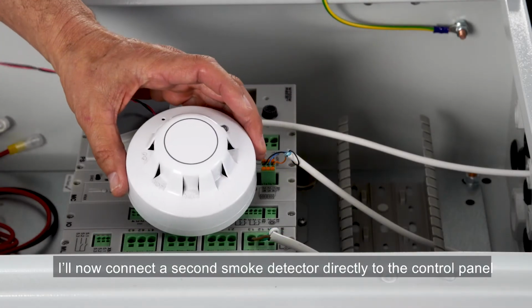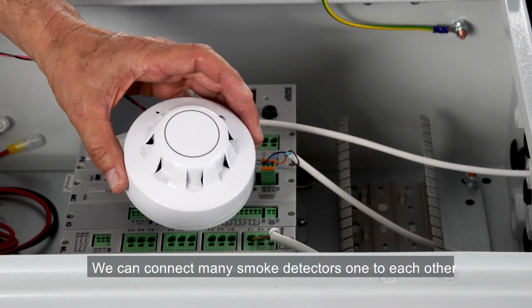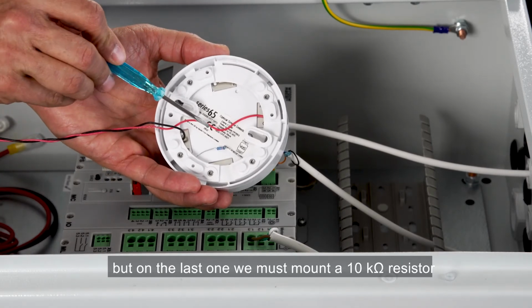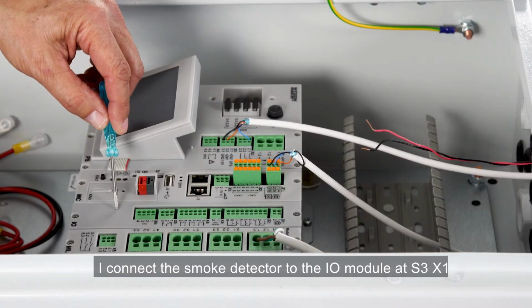I'll now connect a second smoke detector directly to the control panel. We can connect many smoke detectors, one to each other, but on the last one we must mount a 10 kilo ohm resistor in order to be able to monitor the smoke detectors. I connect the smoke detector to the I/O module at S3X1.